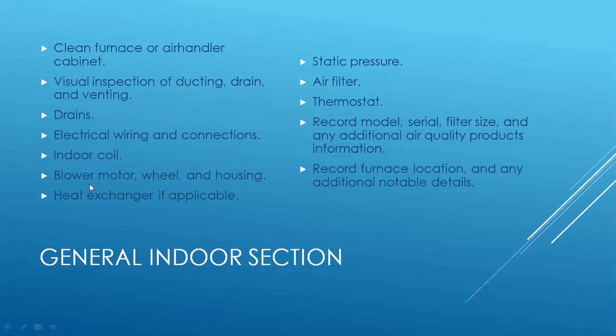Next, you want to check your blower motor, check your outer air vents, make sure they're not clogged up with debris and junk. If it is, get that out of there. Also check your wheel, make sure it's not full of junk and buildup and debris. Just a 1/4 inch buildup on your blades can cause a 20% reduction in airflow. And then also take a look at your housing. If your housing's all nasty, chances are your wheel is going to be nasty. And if that's the case, chances are your indoor coil is going to be the same thing. There again, if you have a gas furnace, take a look at the heat exchanger while you're there. You're right there in front of it.